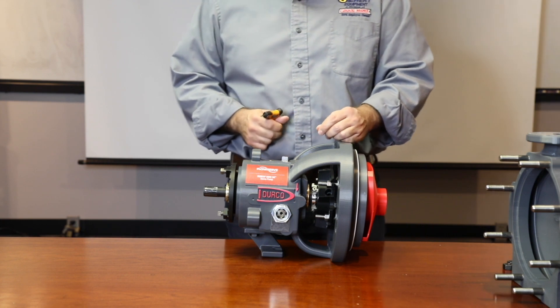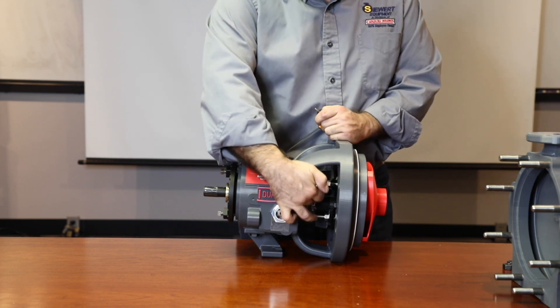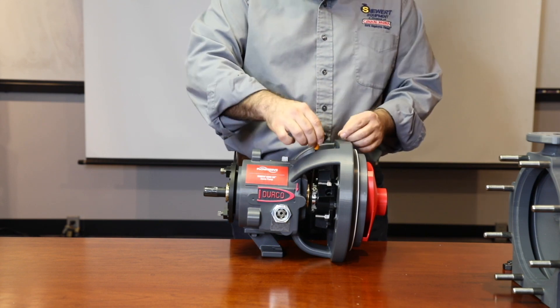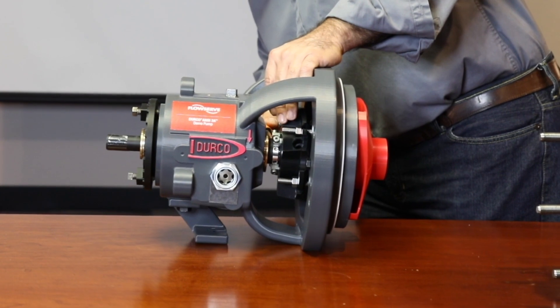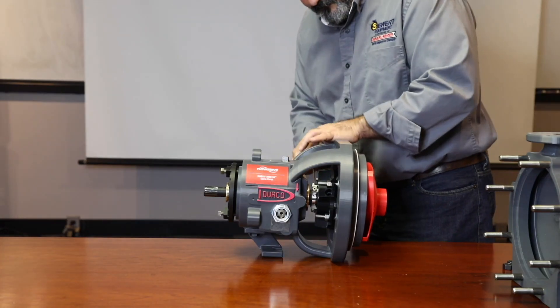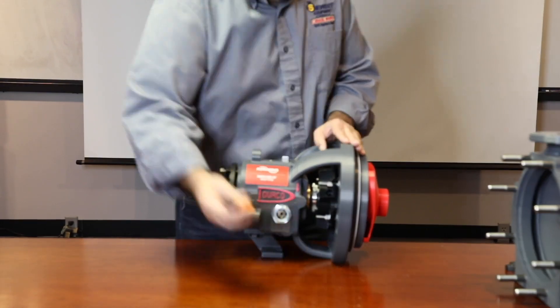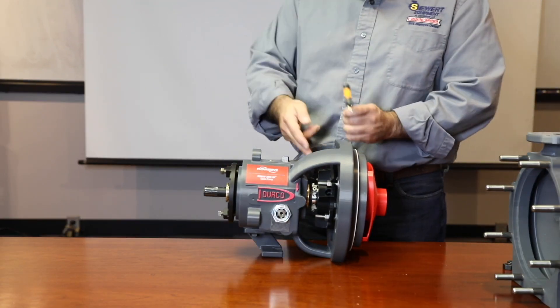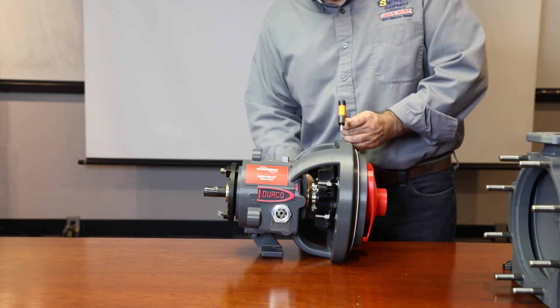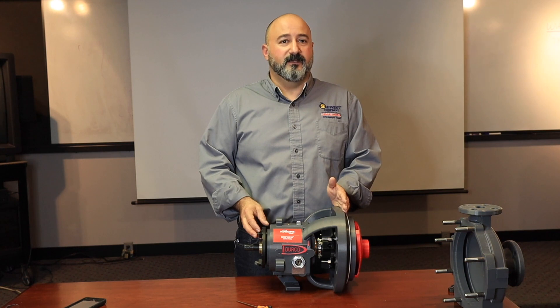Once all four gland bolts are tightened, you can then tighten down the drive collar set screws, remembering to go in an alternating pattern. Once the set screws are tightened down to the recommended torque, you can then remove the four setting clips. The pump is now ready for service.